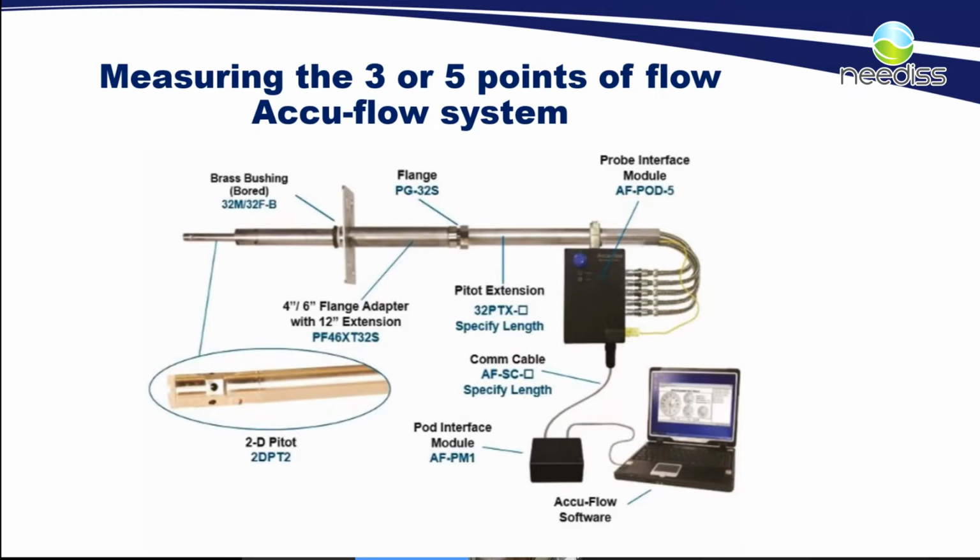And this is something that has been useful here in the US for determining accurate flow rates for things like Performance Specification 11, which is online PM CEMS equipment, or other CEMS type equipment that is going to be permanently installed. Maybe a flow CEMS needs to be calibrated in a stack when it's first installed. That will allow us to get very accurate measurements to be able to create a very, very good calibration for a device like that.